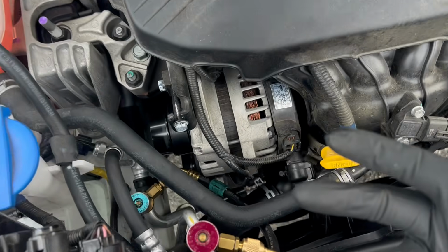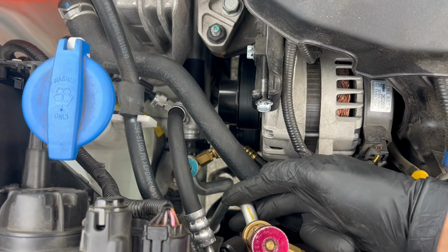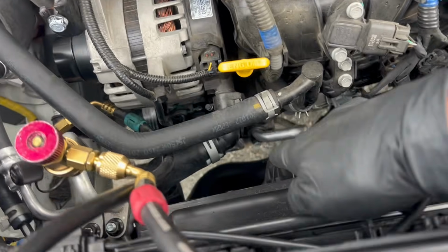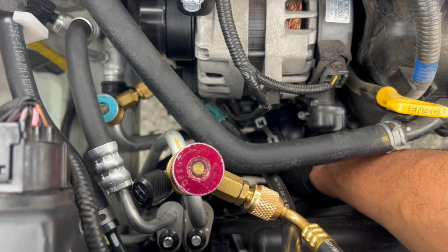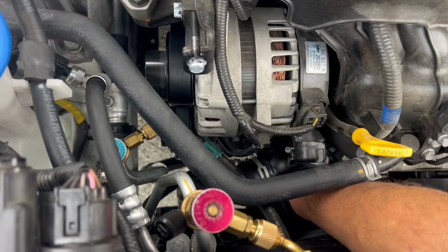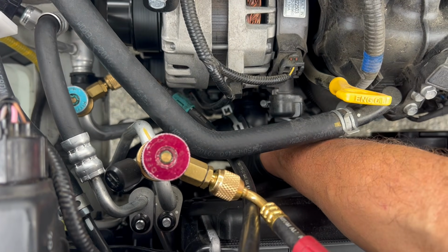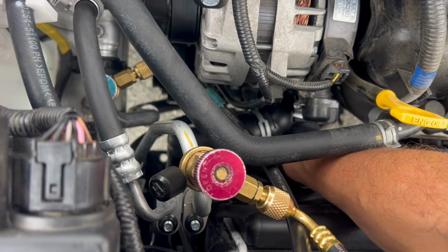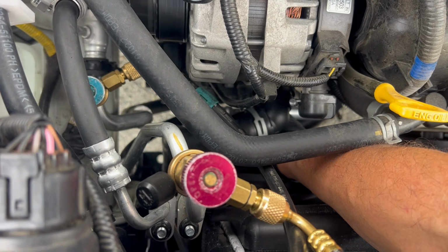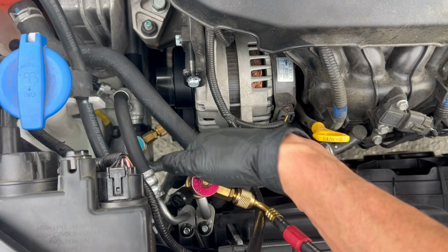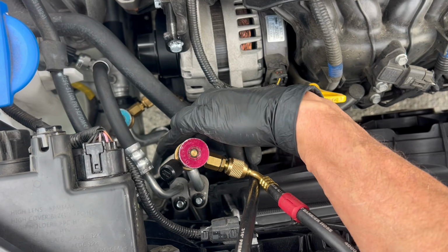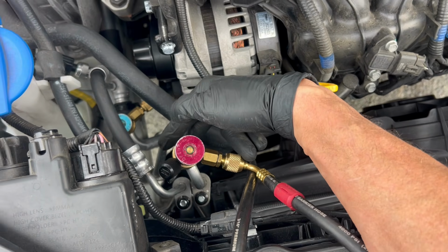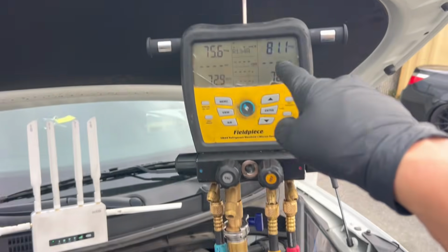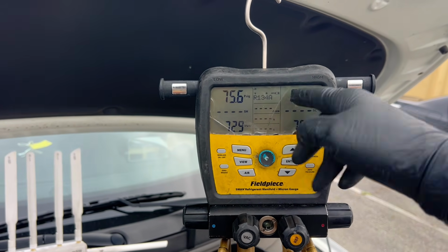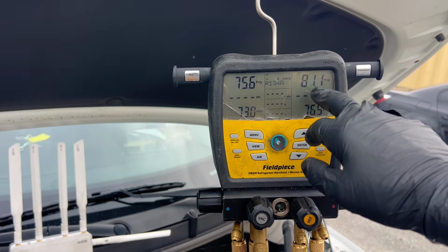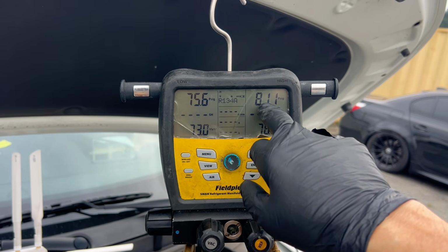I don't have one with me right now, but I would put a clamp-on temperature sensor here, and I would put a clamp-on temperature sensor down here coming out of the compressor. And let's say I had a 199 degrees Fahrenheit temperature at the discharge of the compressor. But then I come over here and I have 120 degrees. So you go, well, 120, and I read up here at the pressure, and it says, I don't know, I'm going to make up a number. It says 118 PSI or 130 PSI.